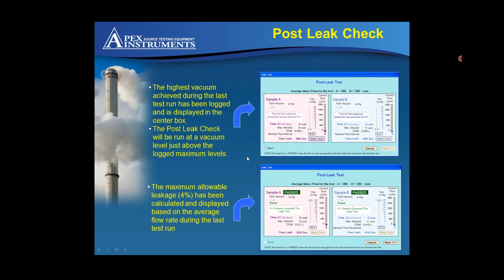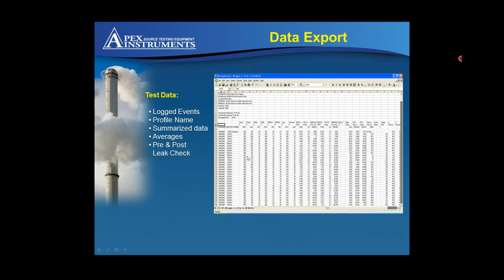This is an example of the output file when the test is completed. We output a readable text file and a CSV file, shown here, which has all the console information, software versions, dry gas meter IDs, trap IDs, temperatures, pressures, and creates a data record every minute. That's more for maintenance, to make sure the system's operating properly. The actual profile you created to set up the test is at the bottom of the data too.